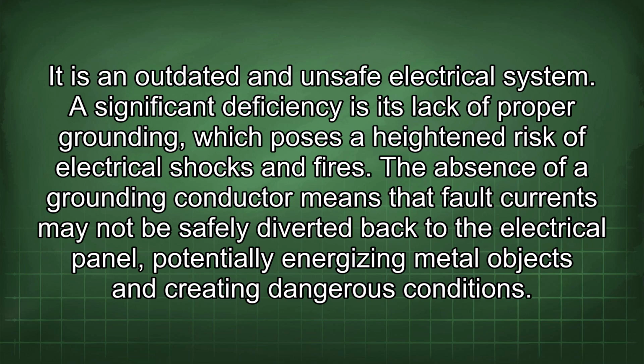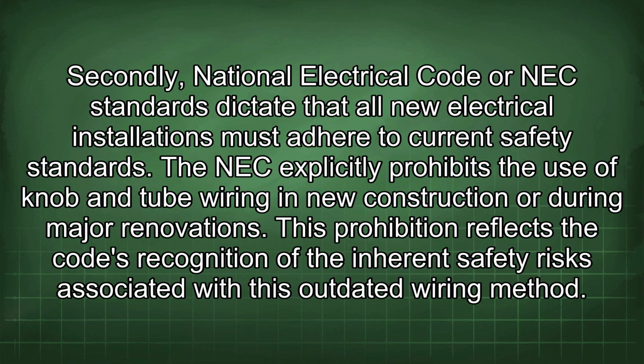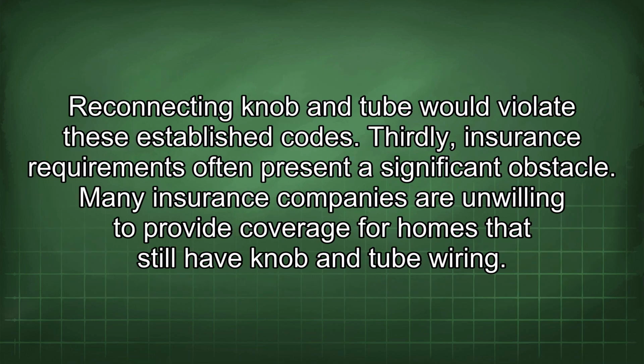The absence of a grounding conductor means that fault currents may not be safely diverted back to the electrical panel, potentially energizing metal objects and creating dangerous conditions. Secondly, National Electrical Code or NEC standards dictate that all new electrical installations must adhere to current safety standards. The NEC explicitly prohibits the use of knob and tube wiring in new construction or during major renovations. This prohibition reflects the code's recognition of the inherent safety risks associated with this outdated wiring method. Reconnecting knob and tube would violate these established codes.